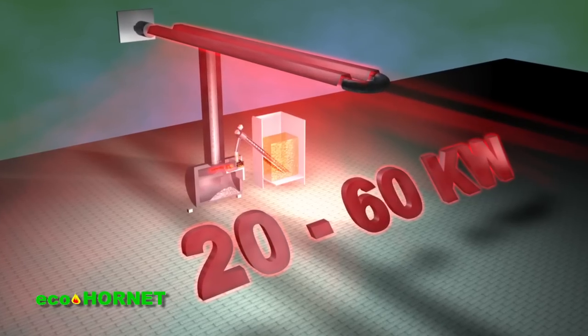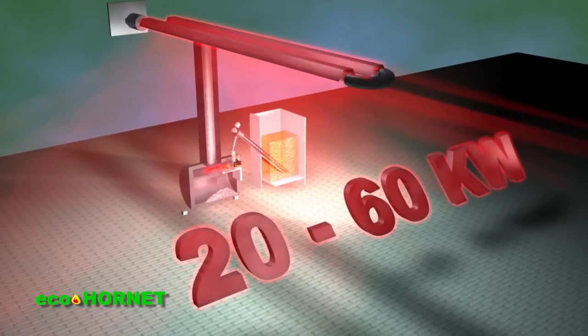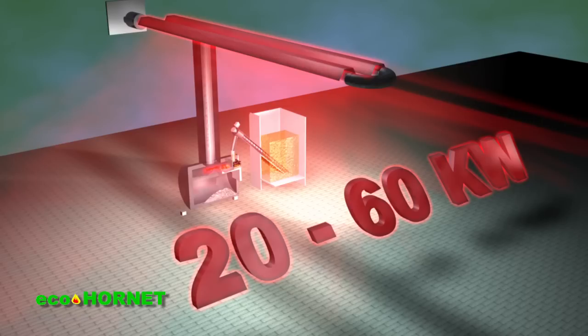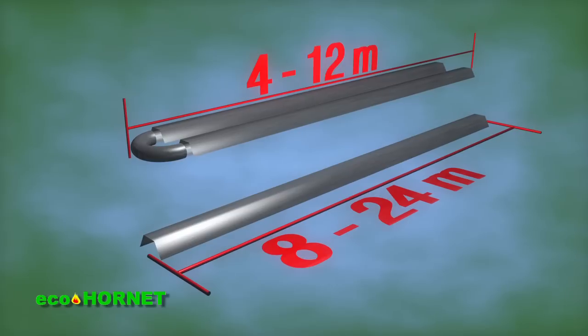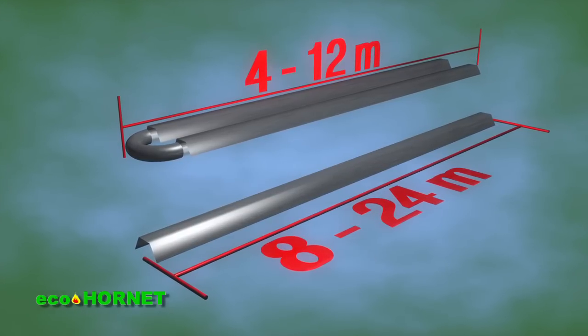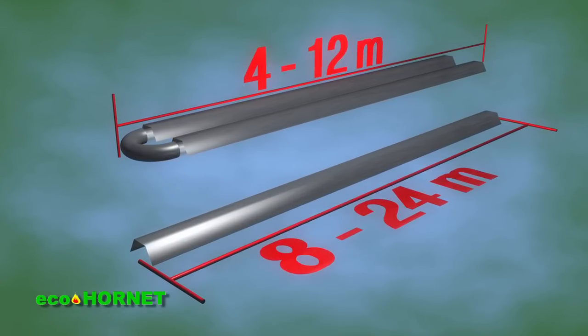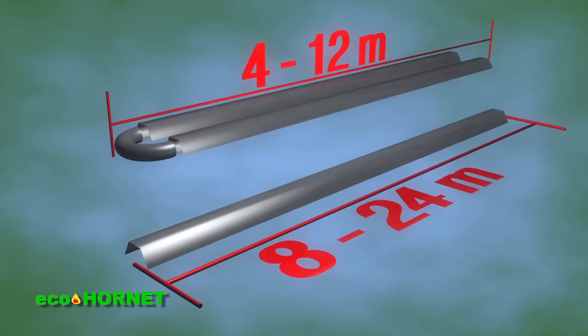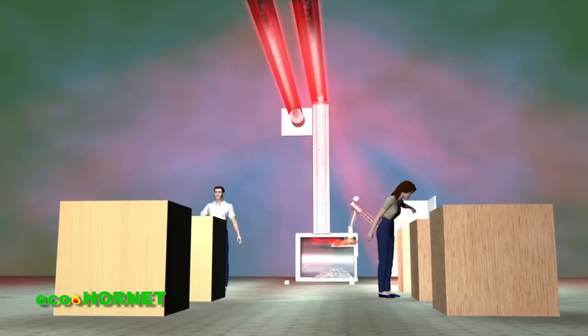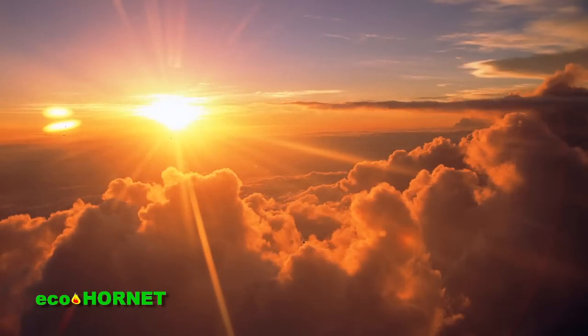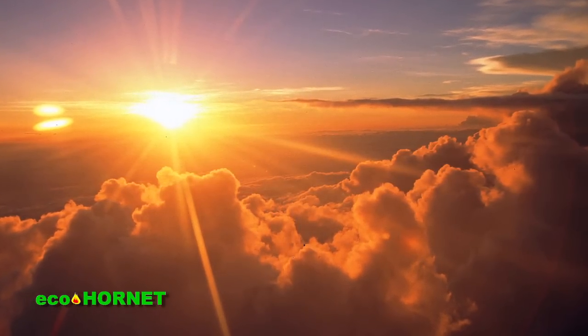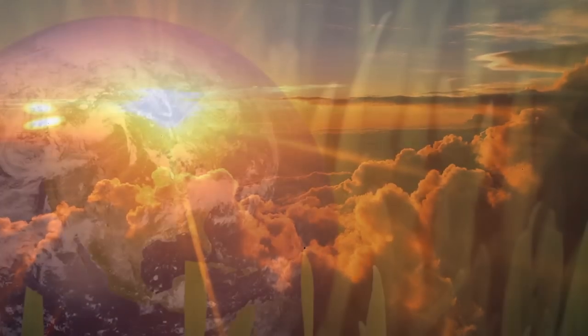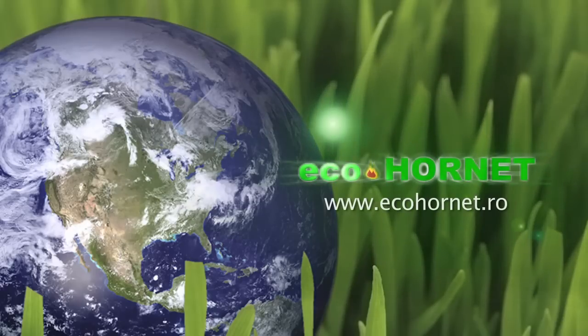The power of the radiant tube burners manufactured by Eco-Hornet ranges between 20 and 60 kilowatts, with U-shaped linear tubes with a length of 4 to 12 meters, or with linear tubes with total lengths between 8 and 24 meters. Radiant tube heating is extremely efficient for large areas, achieving heating identical with that provided by sunlight, without using large volumes of air. Eco-Hornet pellet burners for radiant tubes provide major consumers with a cheap, clean, and efficient heating system.